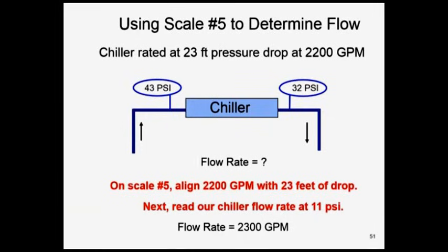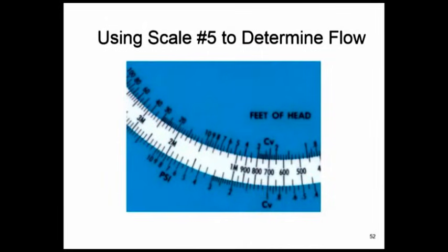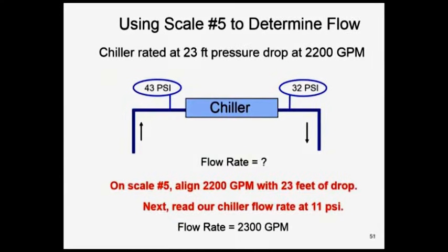Now, 2,300 GPM. I'm going to show you next the setup. Real simple on scale 5. I know that 2,200 GPM is a pressure drop of 10 pounds. And if you look at the pounds on the bottom scale there, you see the 10, and the next one over is 11. That would be the flow rate. We know at 10 pounds is 2,200 GPM, but my actual pressure drop per the gauges was what? 11 pounds. So at 11 pounds, what am I reading? I'm reading 2,300 GPM. So my answer is my pressure drop's higher than design. Design was 10 pounds, and I'm up to 11 pounds.